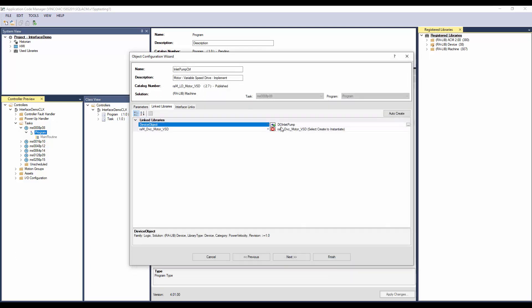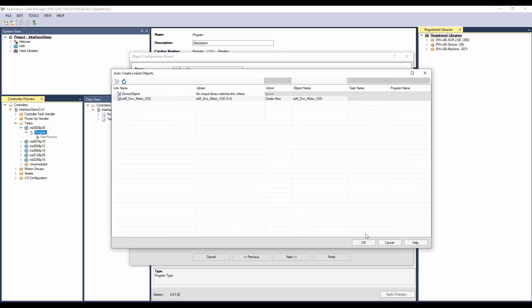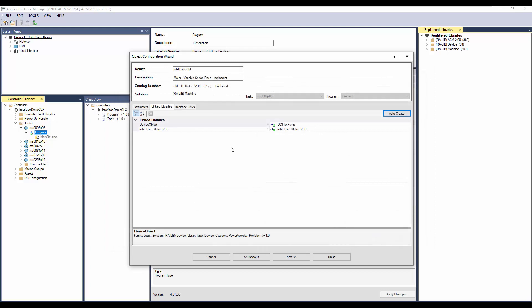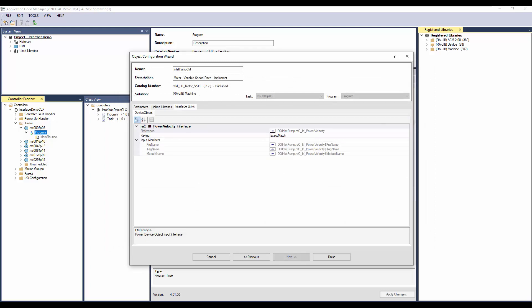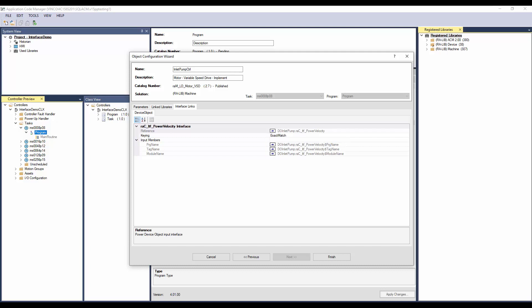I will change the routine name as inlet pump control, so both Motor VSD and PowerFlex 525 device object are placed in the same routine. Add the link library and click finish to complete the instantiation of the device object. Now we have the device object added. I will click auto create to create the rest of the link libraries. In the interface links, no action is required. You can notice the output interface members of device object inlet pump are linked to the input interface members of the Motor VSD. Since the key is selected as exact match, the user cannot modify these fields. I will click finish to complete the instantiation.